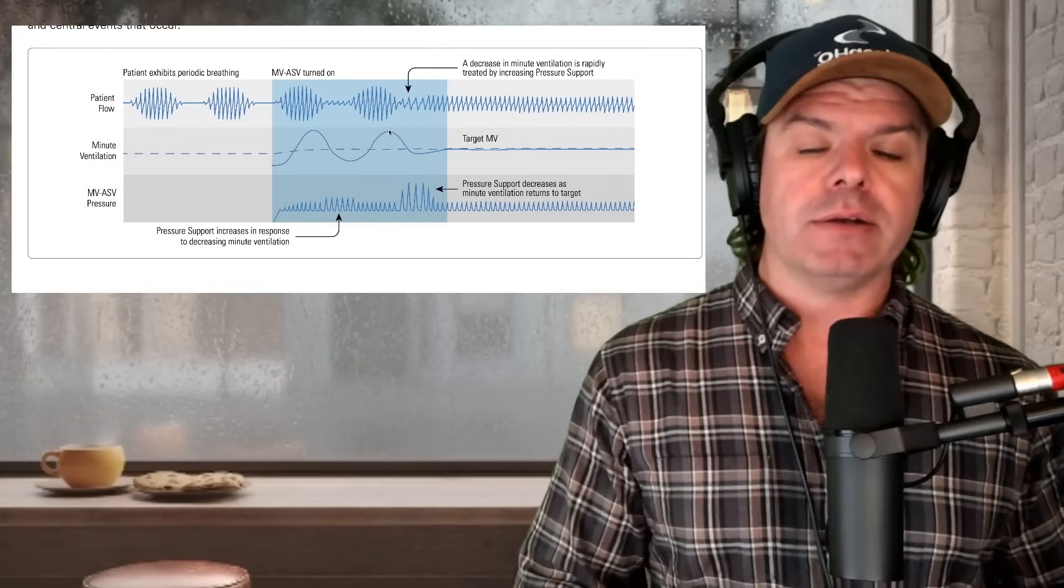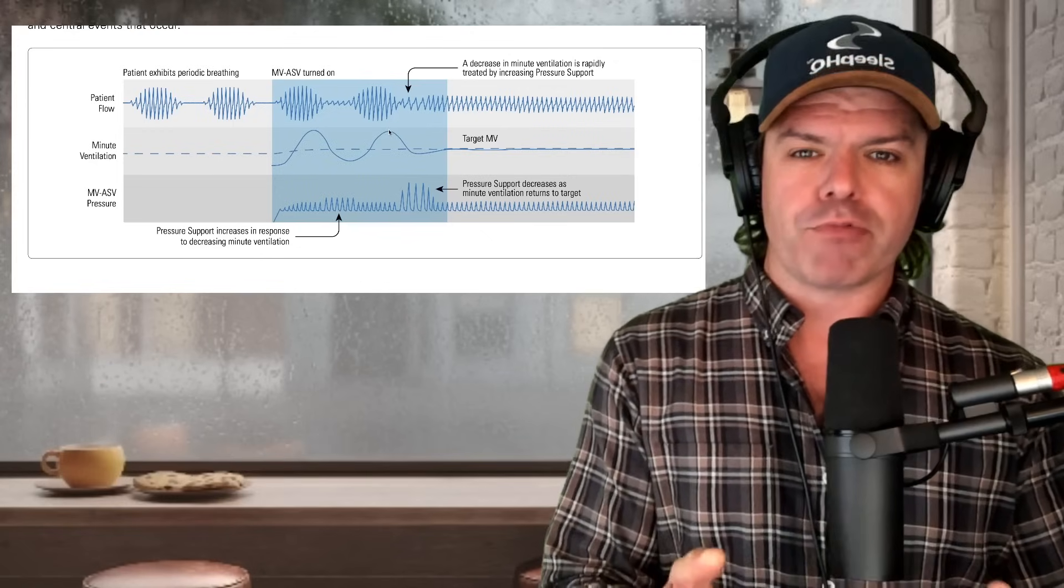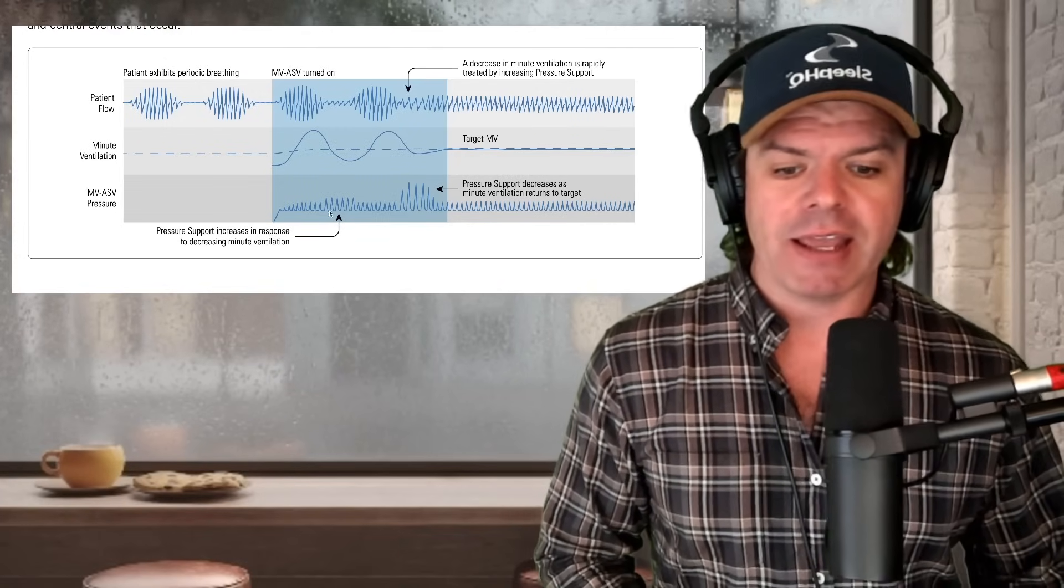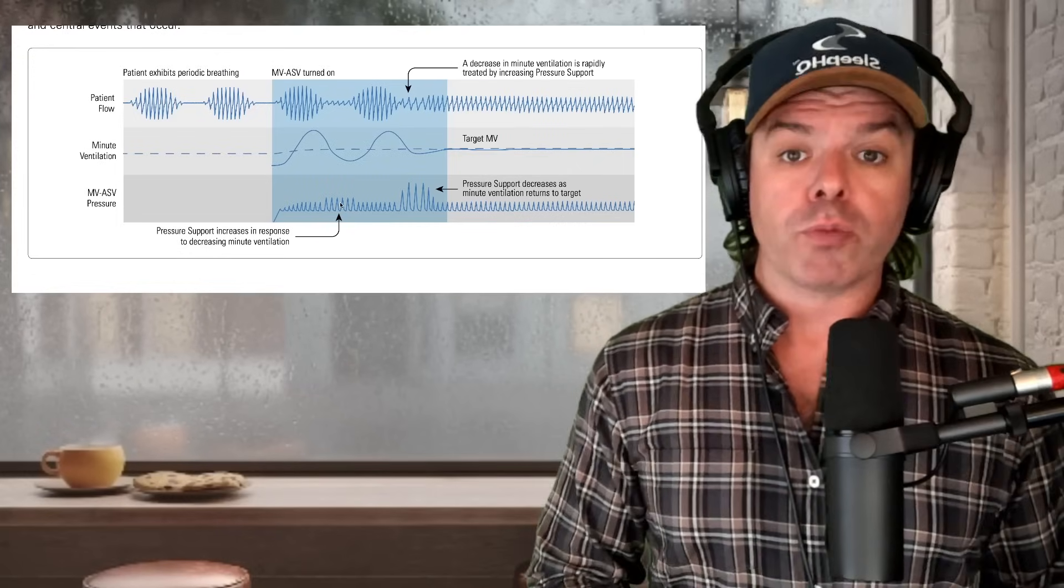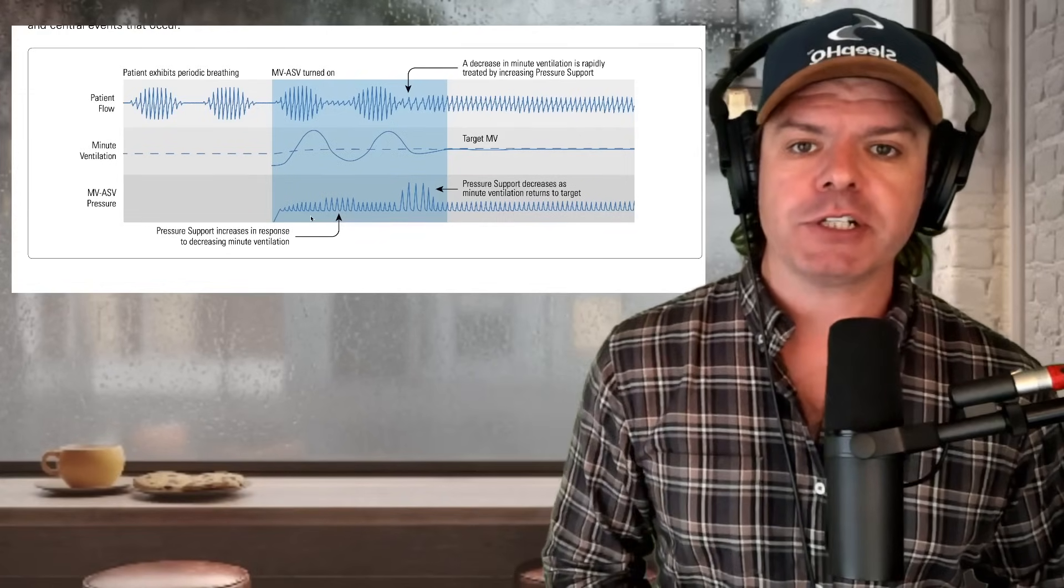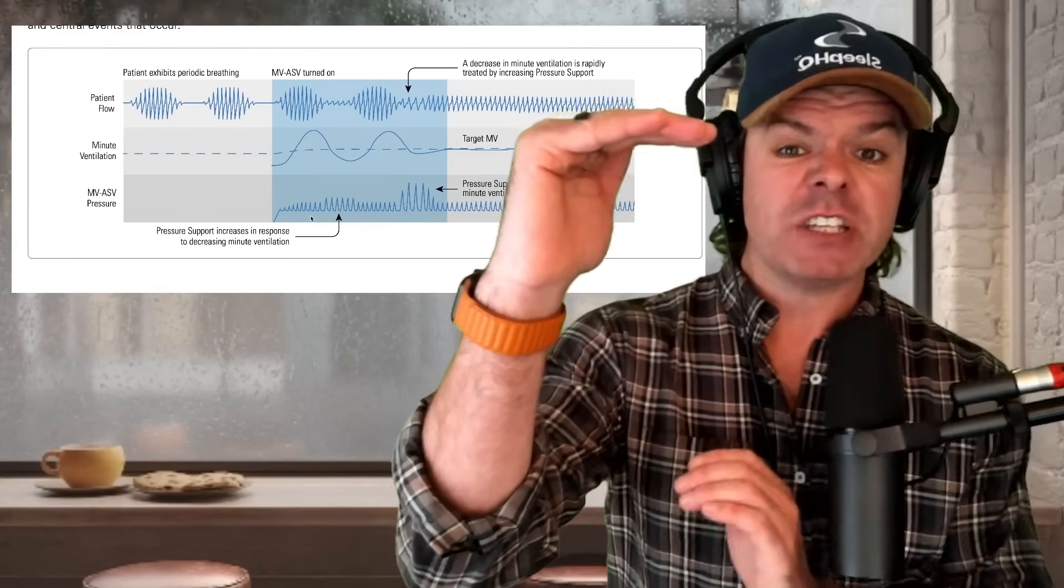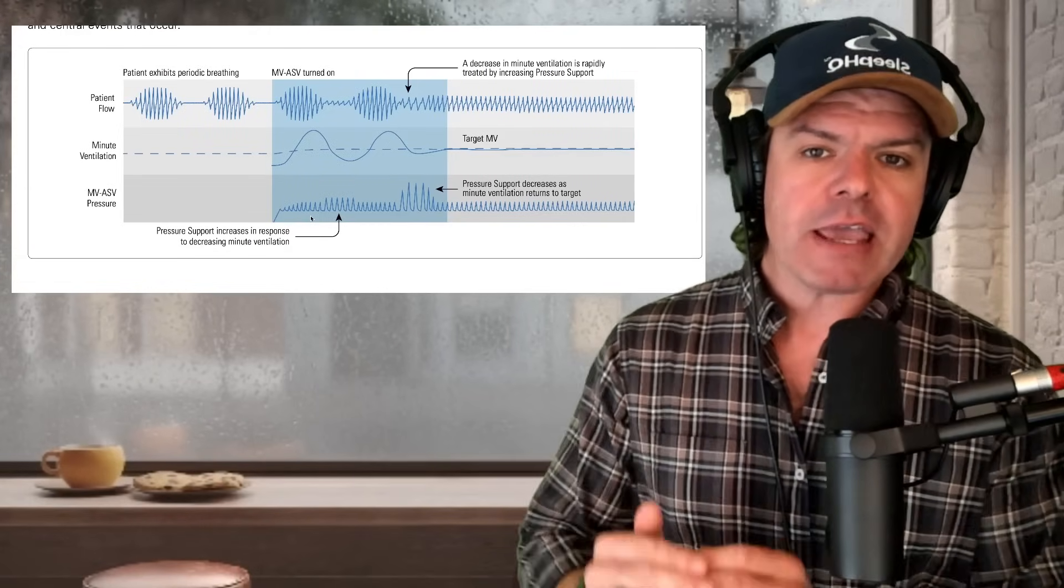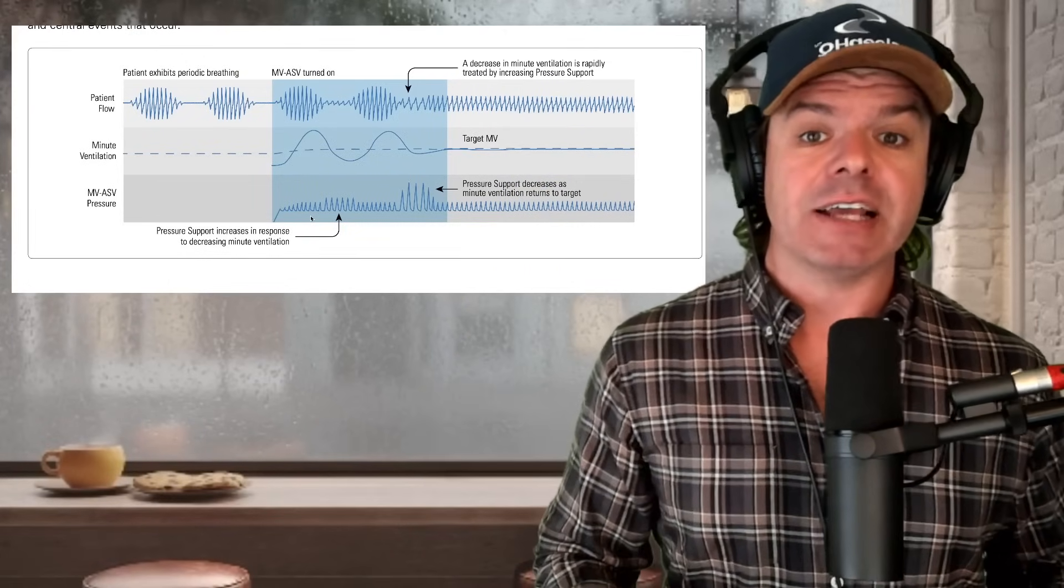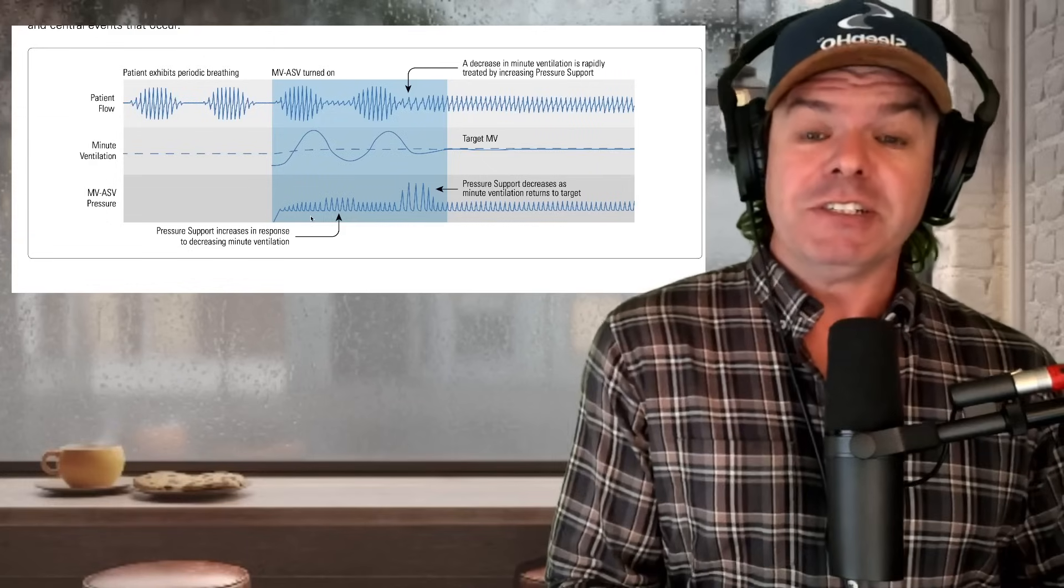So you end up with this wavy pattern and this is something the machine can pick up on. And when it picks up on that, this is when it makes changes, customized changes to the therapy pressure levels to try and break that pattern from happening and even out the breathing as it's doing here. So we'll go down here to the therapy pressure. And the way it does this is with something called pressure support. And pressure support is the difference between IPAP inhalation pressure and EPAP exhalation pressure. So if we have an IPAP of 10 and an EPAP of 6, the difference is 4. And that's the pressure support level, a pressure support level of 4.